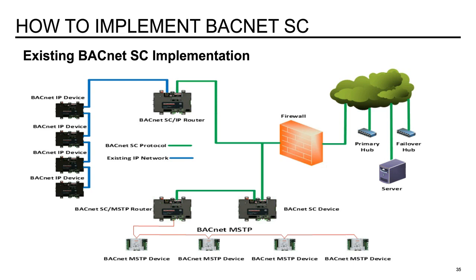Okay. This next question is from Cullen. When connecting BACnet MSTP networks through a BACnet SC router, will a BACnet device table need to be established? No, because you use the table when you're trying to broadcast across multiple networks. And with BACnet MSTP devices connected to the BACnet SC router, that is one network. So all of those devices would just connect to that SC router. There won't be a need for a broadcast table or distribution table because you're not trying to go across networks.